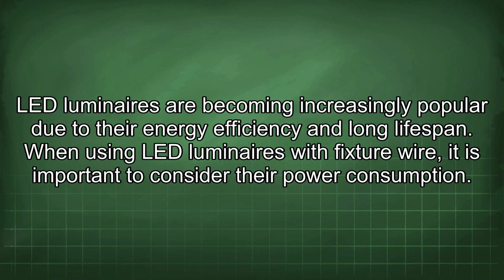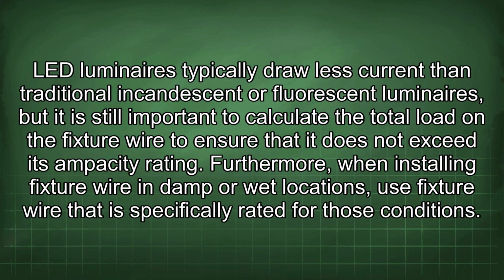When using LED luminaires with fixture wire, it is important to consider their power consumption. LED luminaires typically draw less current than traditional incandescent or fluorescent luminaires, but it is still important to calculate the total load on the fixture wire to ensure that it does not exceed its ampacity rating.